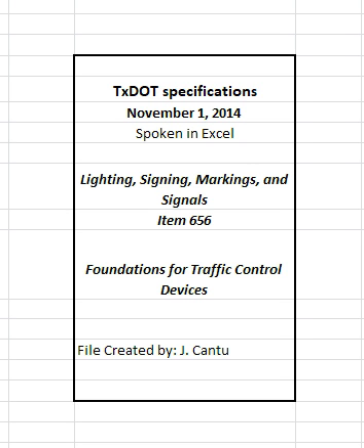Allow concrete for pedestal poles and roadside flashing beacon assemblies to cure at least 7 days before placing bases and poles on the foundation unless otherwise permitted in writing. Allow concrete for traffic signal controller foundations and small roadside signs to cure at least 4 days before placing cabinets and posts on the foundation unless otherwise permitted.